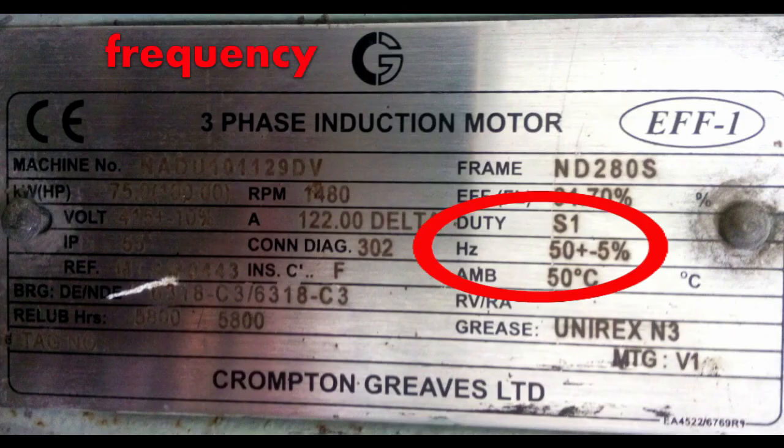Next comes the frequency. Generally, on the nameplate, it is written 50 hertz plus minus 5% or 60 hertz plus minus 5%. If it is written 50 hertz plus minus 5%, that means you can run the motor in this range, 47.5 hertz to 52.5 hertz. Only then your machine will give good efficiency.